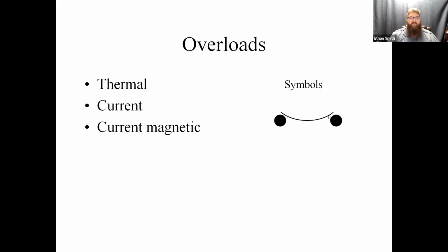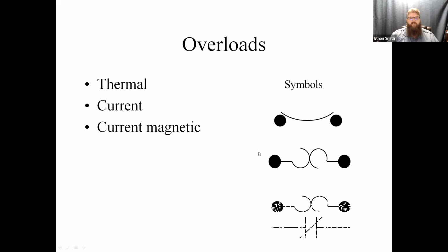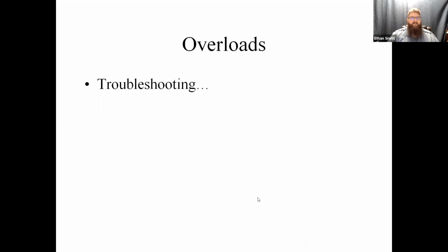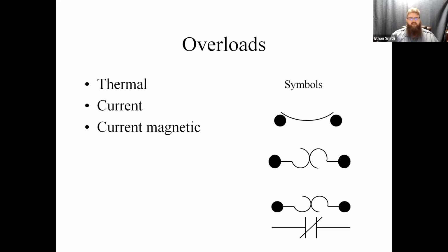When the current gets high enough, this little metal reed will actually coil up and separate itself from that other contact. Current sensing overloads are simply two of those little bimetal discs a lot of times, and they will curl and separate from each other under heat, which would be an indication of high current. Current magnetic ones are using their circuit to break a set of relays. So this is just a solenoid activated current sensing relay. Okay, but in the end, guys, these are all just glorified switches, thermally activated switches, whether they're direct acted thermal like this one, or electrical heat generation thermal overloads like this one. They're all just switches. They're open or closed. They have two positions. You can sense voltage through them or you can't.